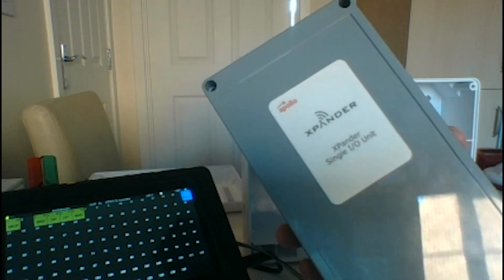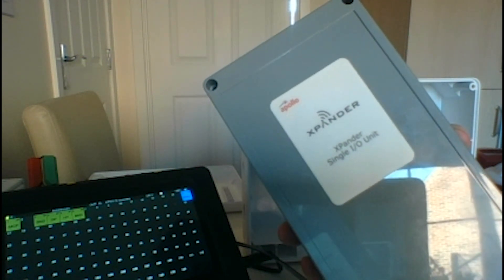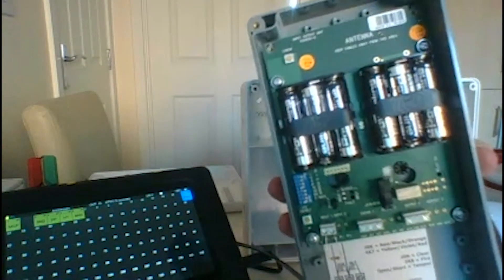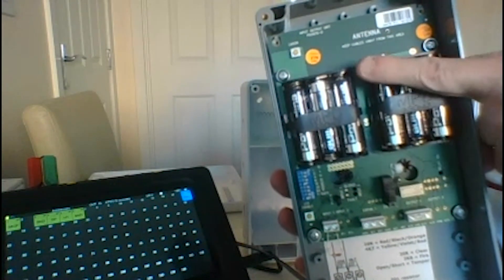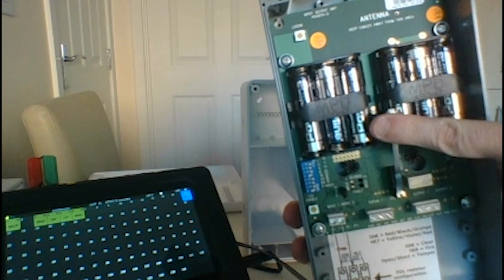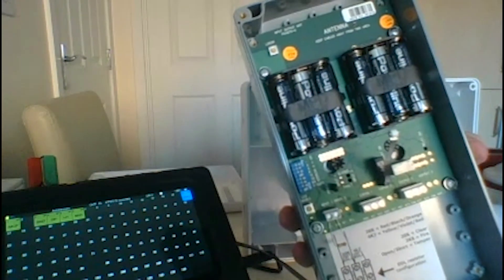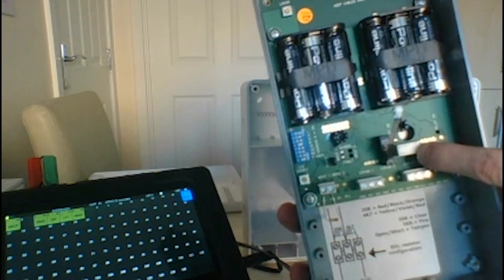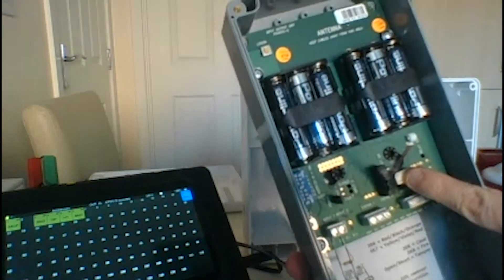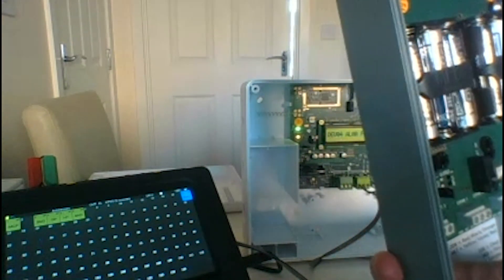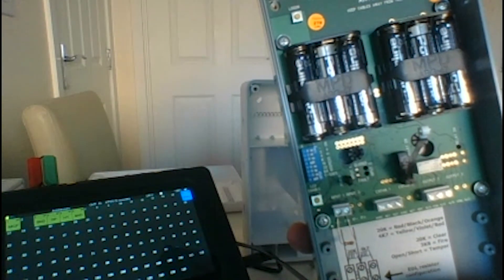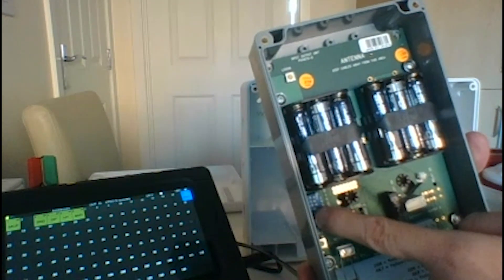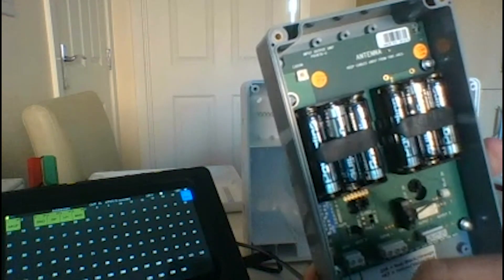Inside you've got your battery packs at the top - six double A alkaline batteries. There's a tamper spring on here so it will come up with a tamper once it's added on. You can see your relay here, it's going to switch 24 volts at 1 amp, and you've also got your end-line resistor on the input side - a 20k end-line resistor. You've got your address mechanism on the side here, this one's set up for address 8.